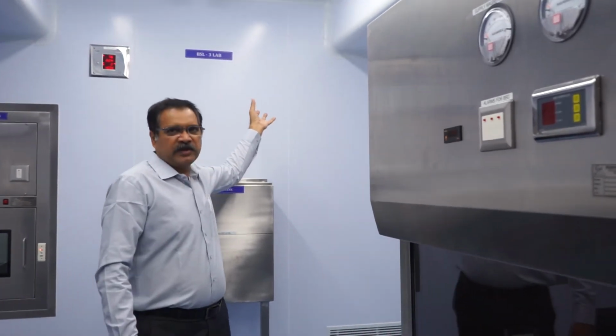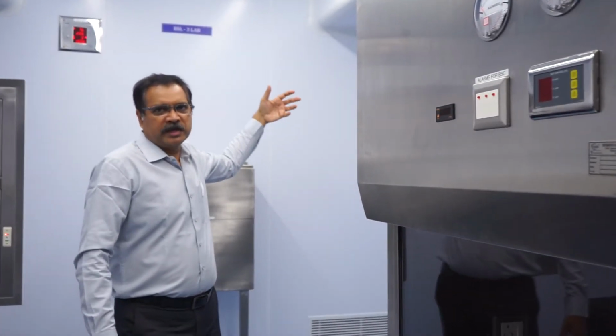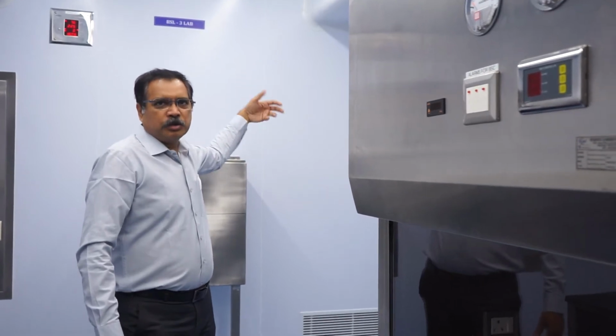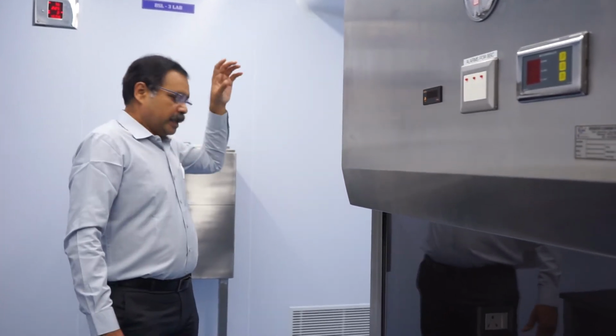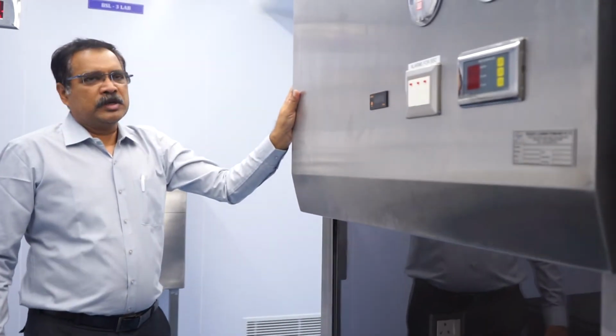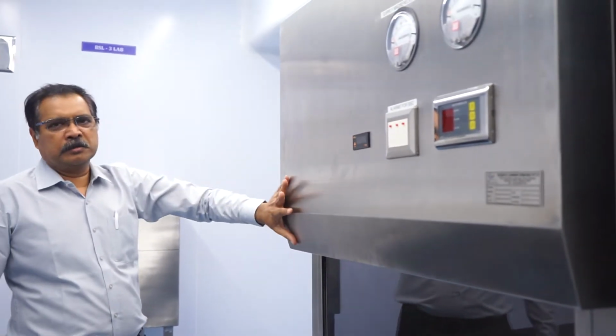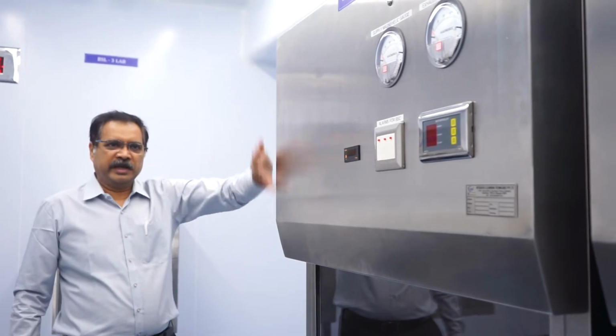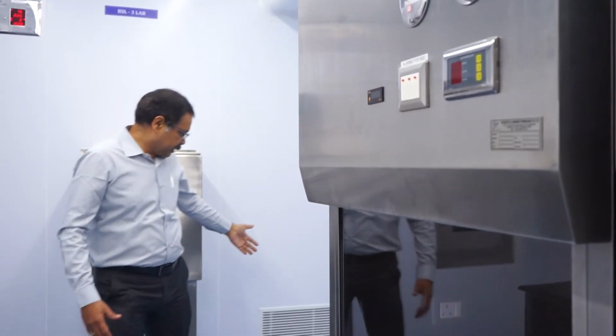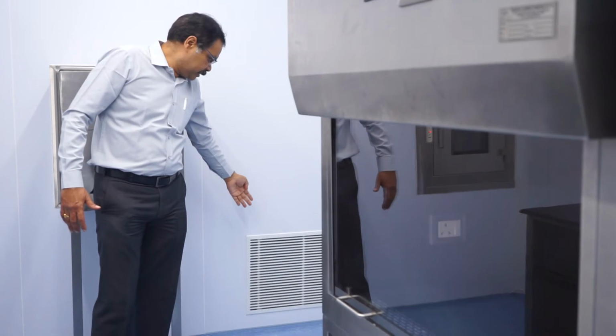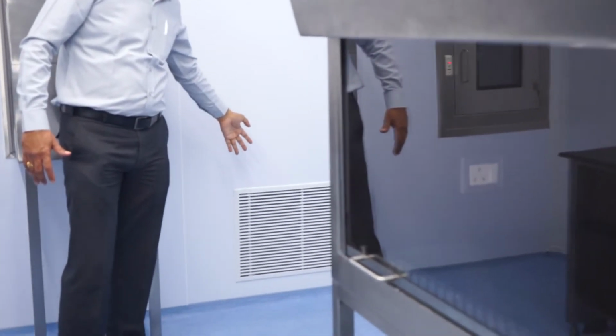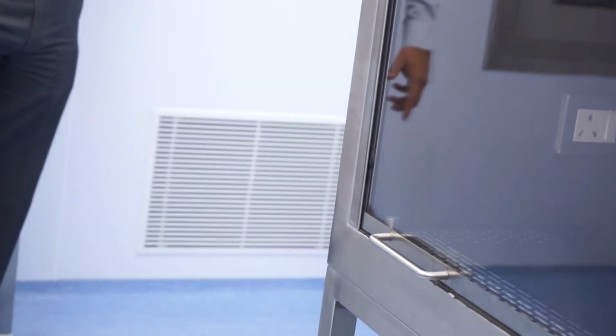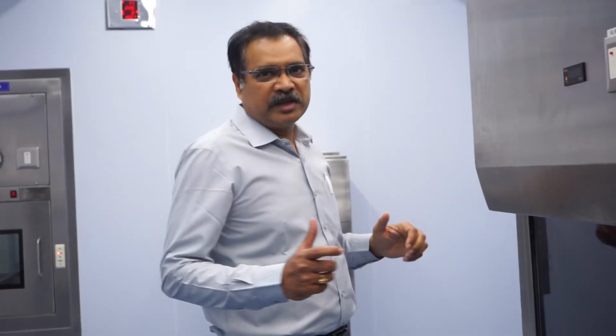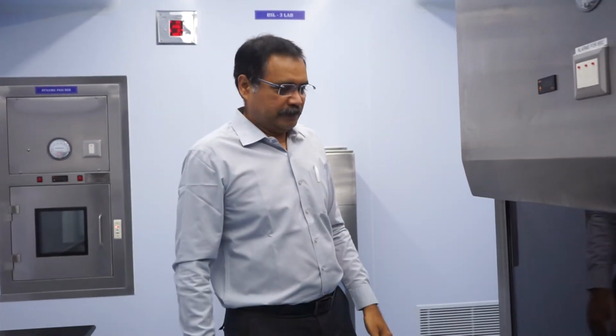to that exhaust fan, and through the HEPA filter and heater and UV light it is exhausted out. When the biosafety cabinet is taking care of some quantity of air exhaust, the balance air is taken care of through this return air provision, and this total exhaust is balanced by the exhaust fan by providing a variable frequency drive in the exhaust fan.